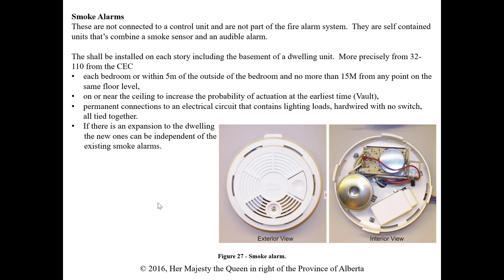Smoke alarms are different from smoke detectors — a smoke alarm is self-contained, combining a smoke detector and audible alarm in one device, used in residential applications without a control panel. Per CEC rule 32-110, they shall be installed on each floor including the basement of a dwelling unit, in each bedroom or within five meters outside a bedroom, and no more than 15 meters from any point on the same floor level, on or near a ceiling. They are permanently connected to an electrical circuit containing lighting loads — hardwired with no switch.